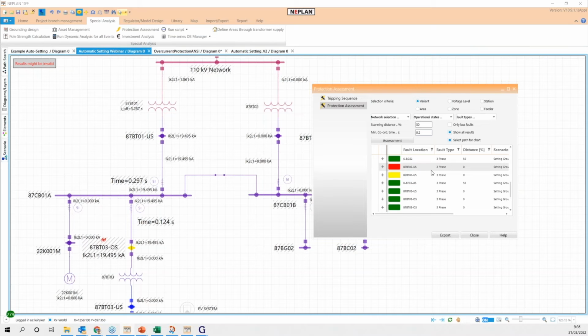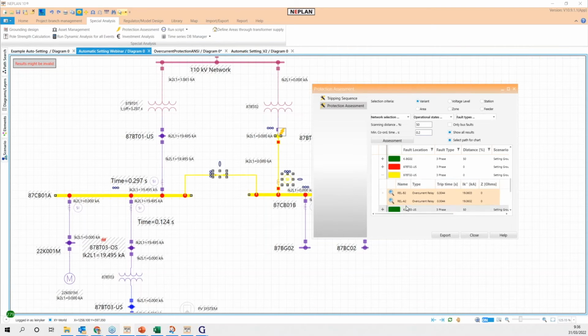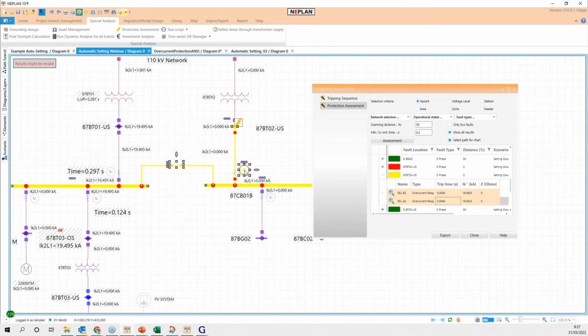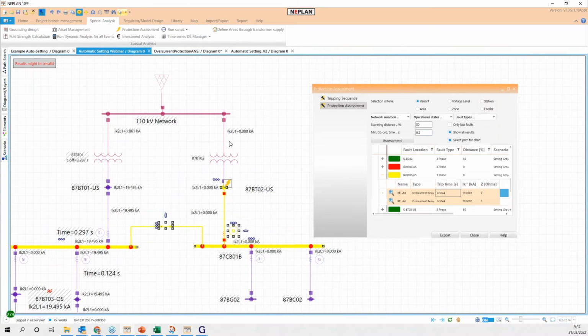If we implement the protection assessment, we can see some results. Let me present what would happen if everything works well, and what would happen in these kinds of scenarios where the software shows a yellow or red message. This case, for example, means that if we have a fault in this node, the operation between both relays, because we can see that this relay and this relay have the same setting, so they will have the same time. So this example is showing that the difference between both protections is not bigger than 200 milliseconds, but the reason is clear. The reason is clear because we don't have any protection here. That means that if we have a fault in this location, we have to clear the fault with the protection that we have to add here on the primary side of the transformer.